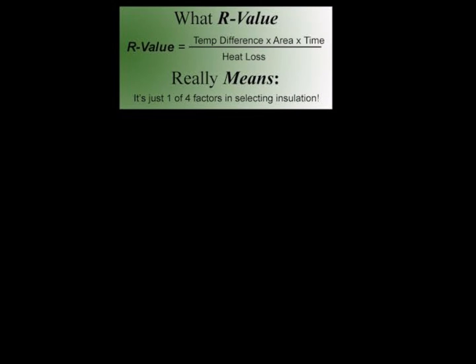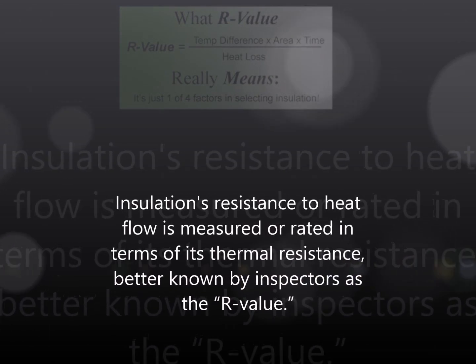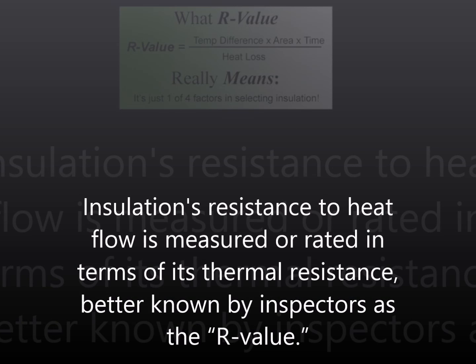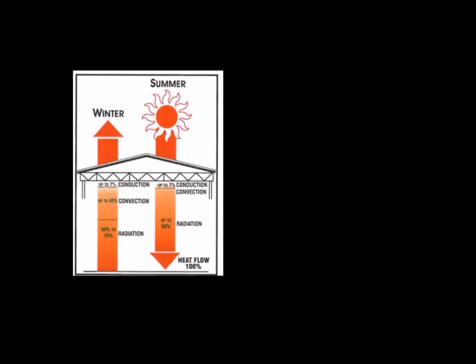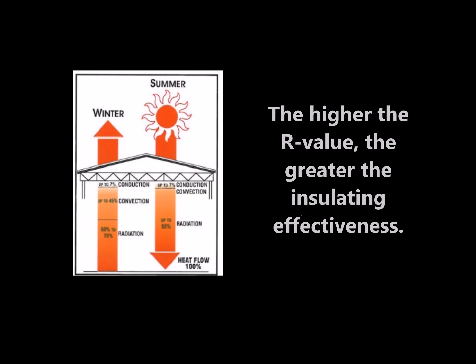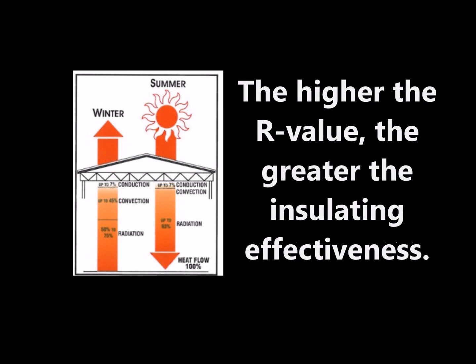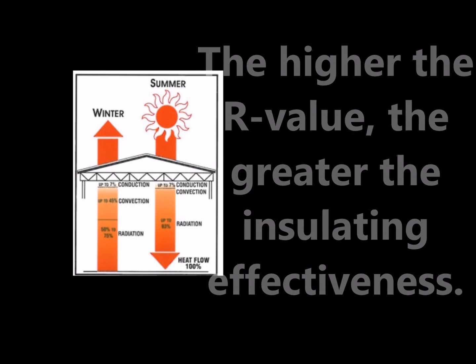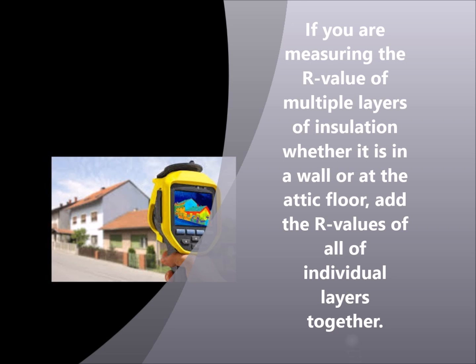Insulation's resistance to heat flow is measured or rated in terms of its thermal resistance, better known by inspectors as the R-value. The R-value is an indicator of insulation's resistance to heat flow — the higher the R-value, the greater the insulating effectiveness. The R-value depends on the type of insulation, which includes its material, thickness, and density. If you are measuring the R-value of multiple layers of insulation, whether in a wall or at the attic floor, add the R-values of all the individual layers together. The installation of additional insulation increases the R-value and the resistance to heat flow. The effectiveness of the insulation's resistance to heat flow also depends on how and where the insulation is installed.